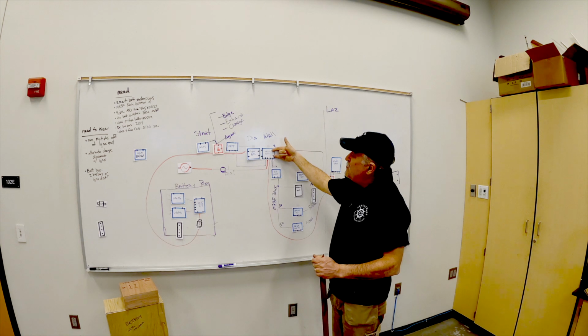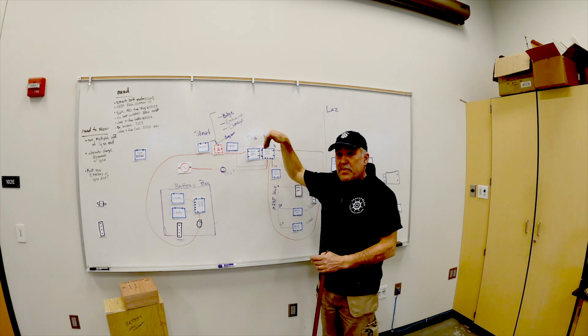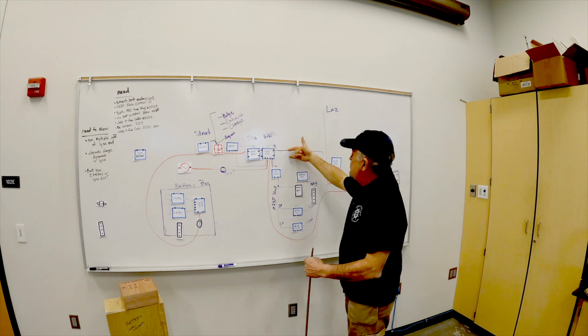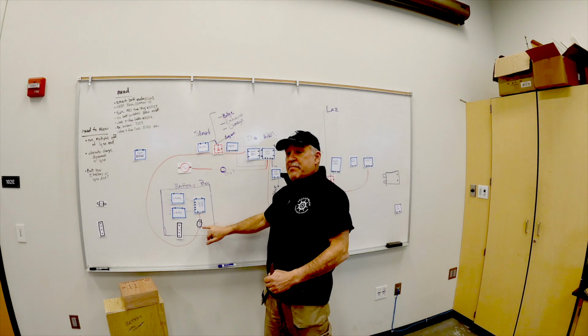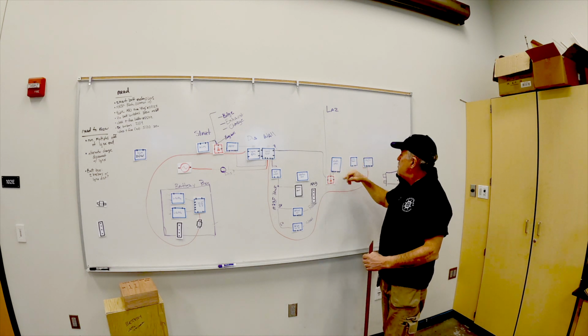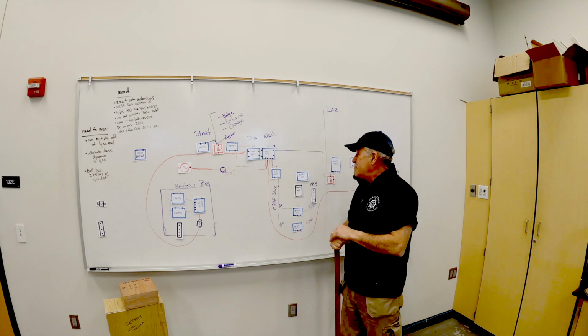I don't know that I can come off the end of a Lynx distributor to power up a MultiPlus. These things are designed to lay together in a system, and all your outputs are designed to go out the bottom, or the top if you were to invert the lid. I'm hoping that I can attach onto the ends and have two cables come out the end that I'll feed my MultiPlus. Its OCP will live back here in the box, but I'll have a local disconnect switch because this will be in the lazarette of the boat. These three items, the isolation transformer, MultiPlus, and the Skylla battery charger, will all live in the lazarette near shore power. So this is mostly DC, and this is our plan today.